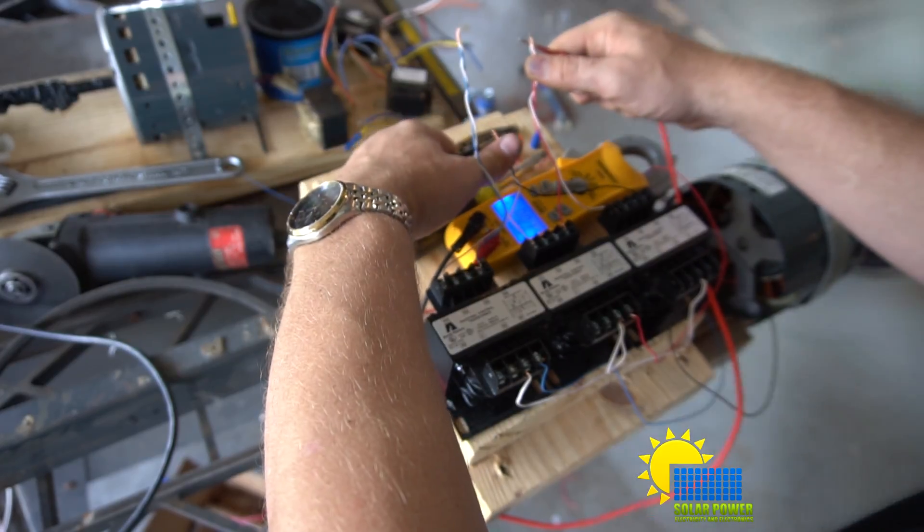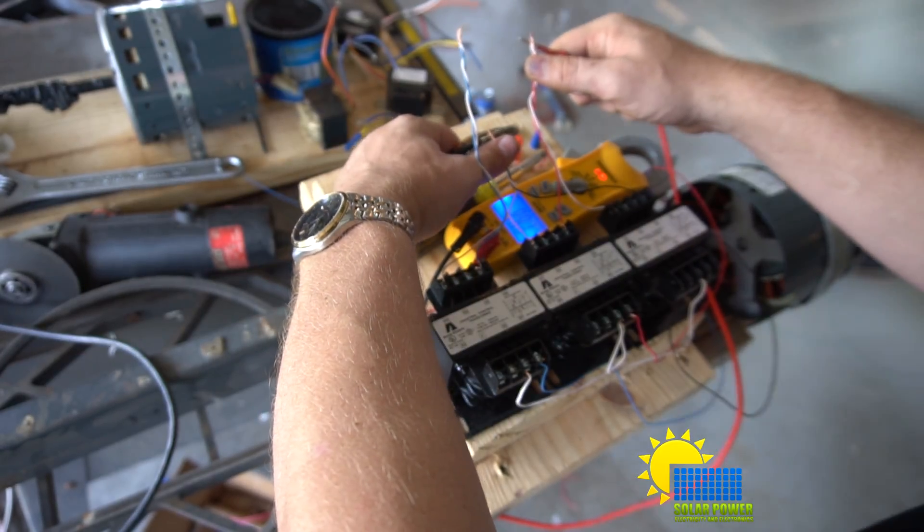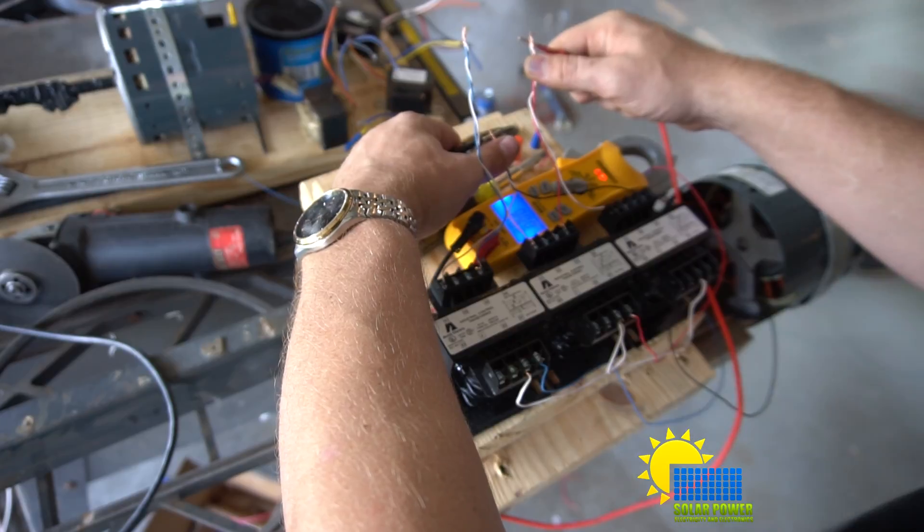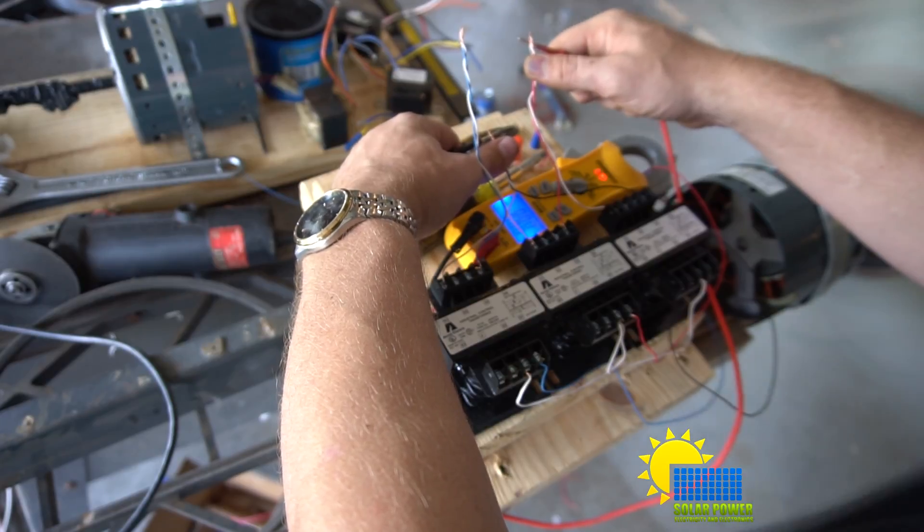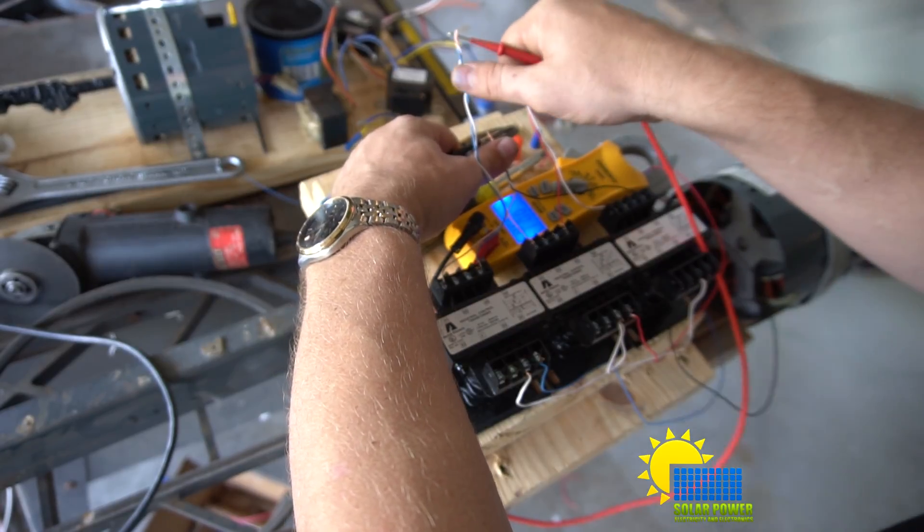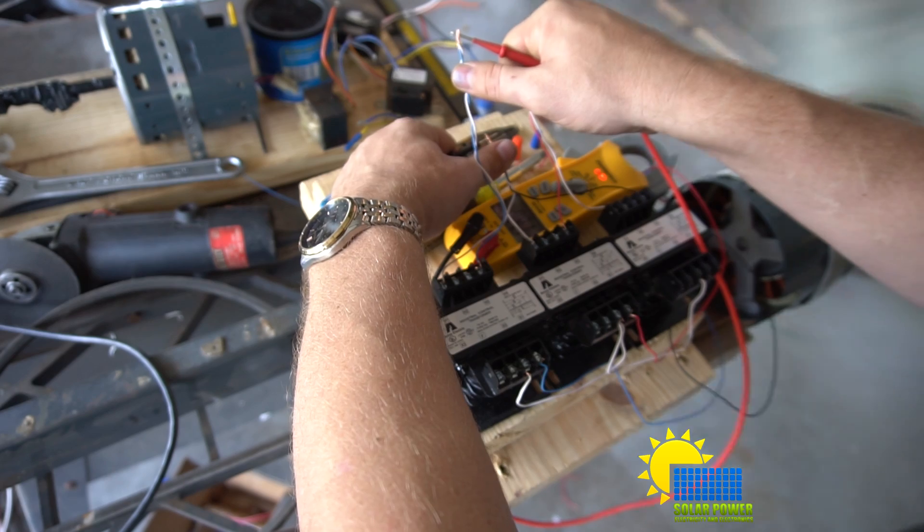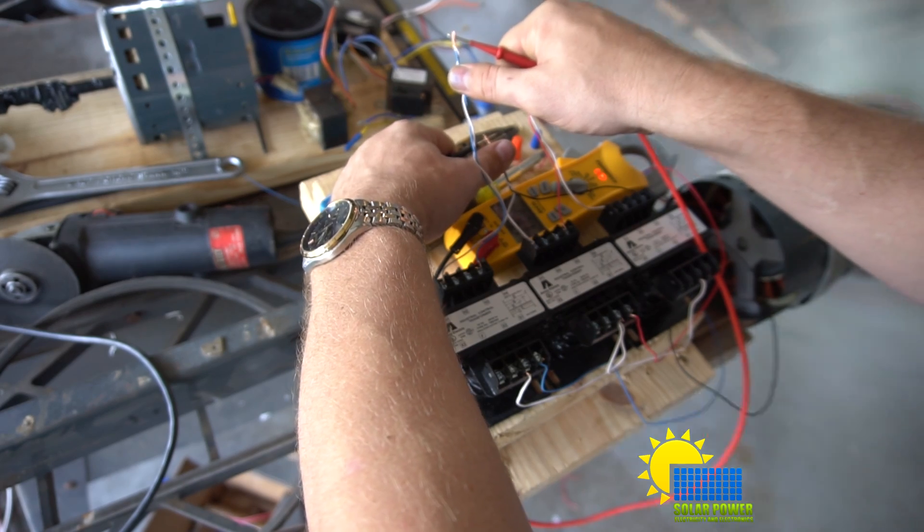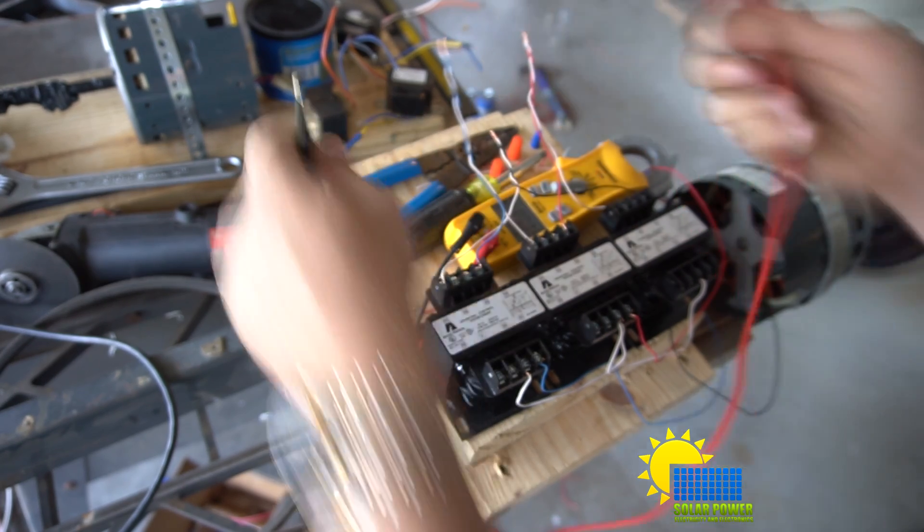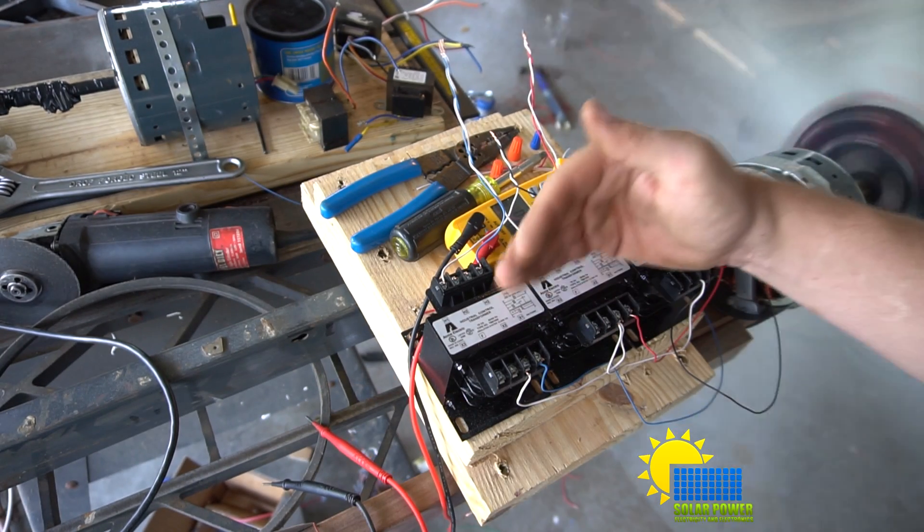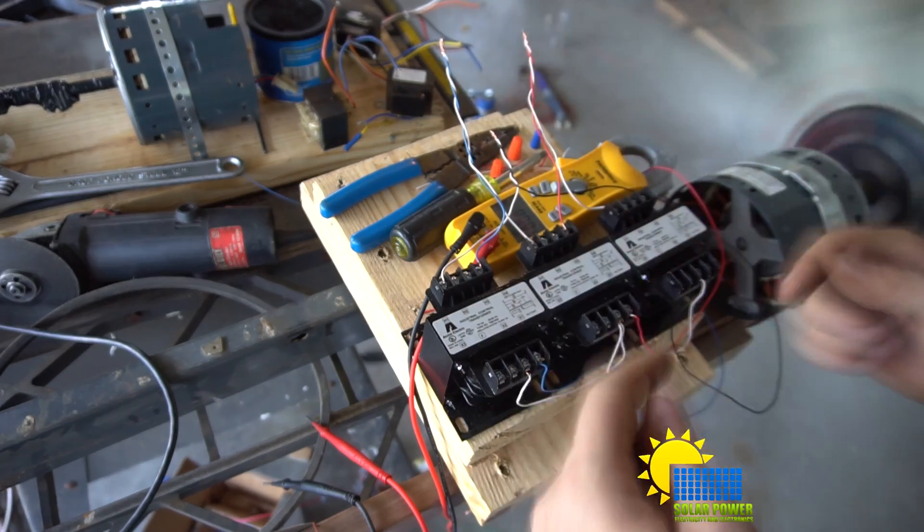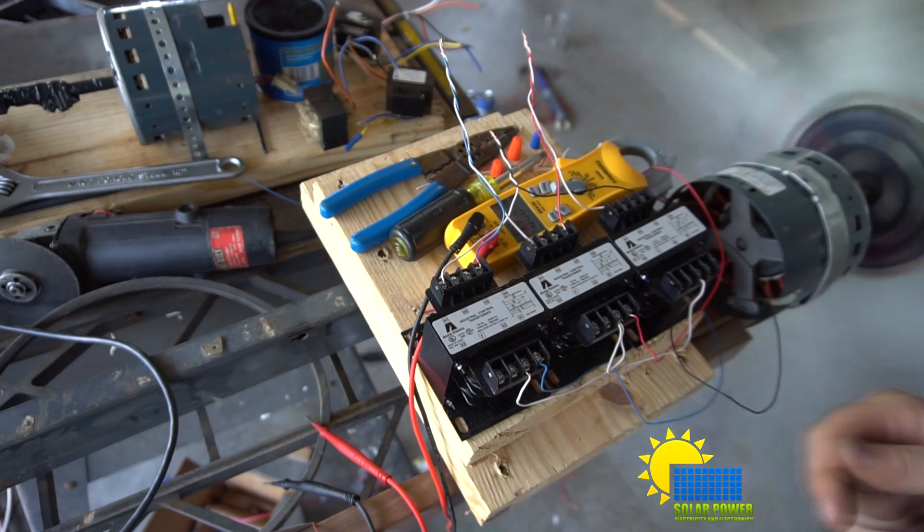But when it reaches up to our power output, we can test our voltages. We got 68 volts, which is absolutely magnificent. Let's check the other phases. 68 volts again. Let's check the last phase. 67 volts, 68 volts again. All right, so we've got our power output in three-phase at 68 volts.